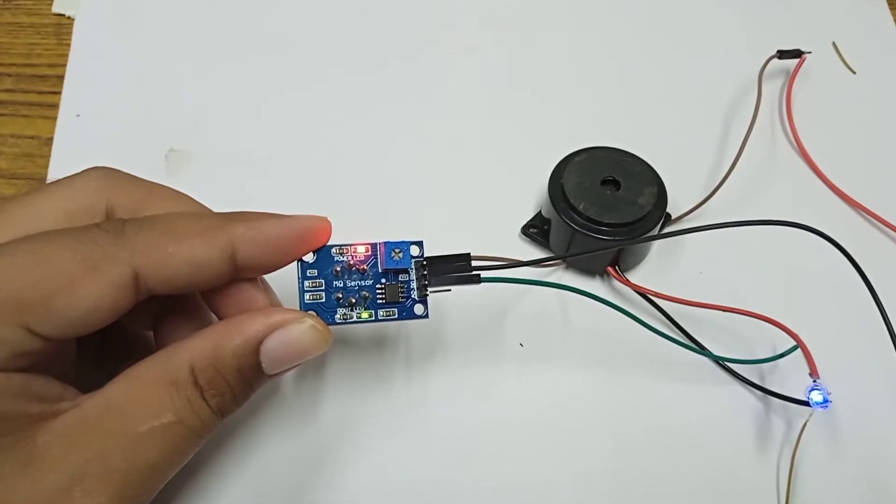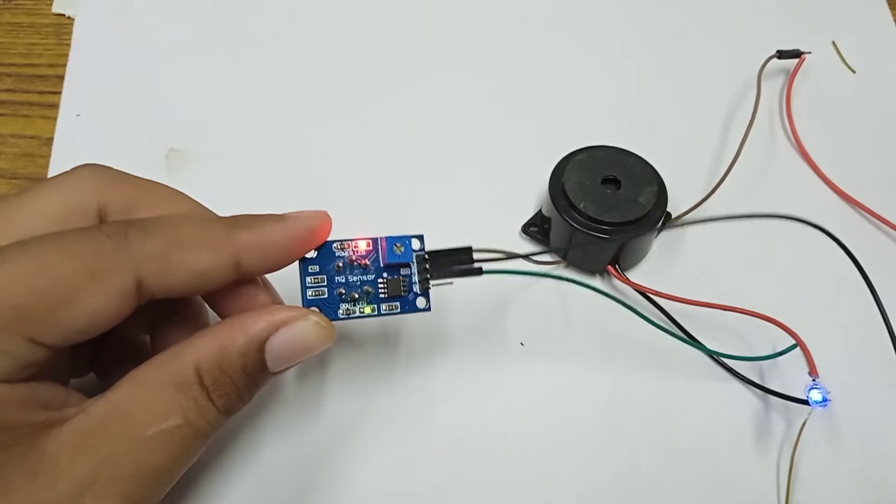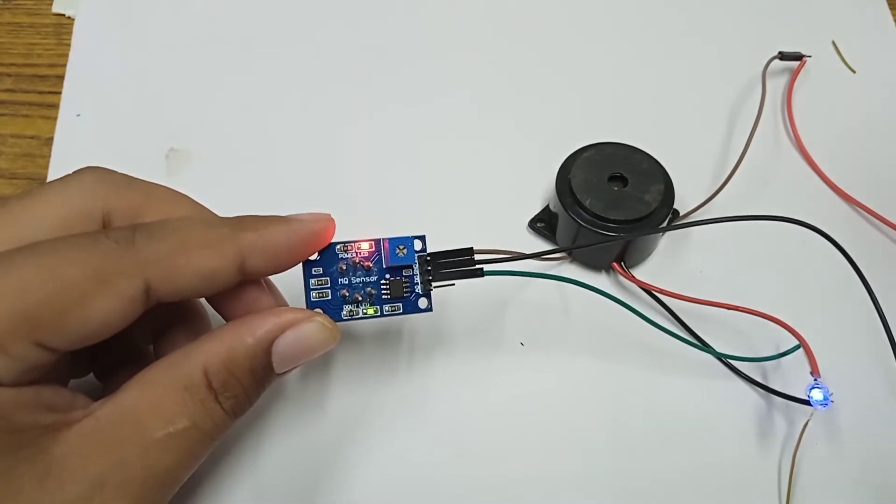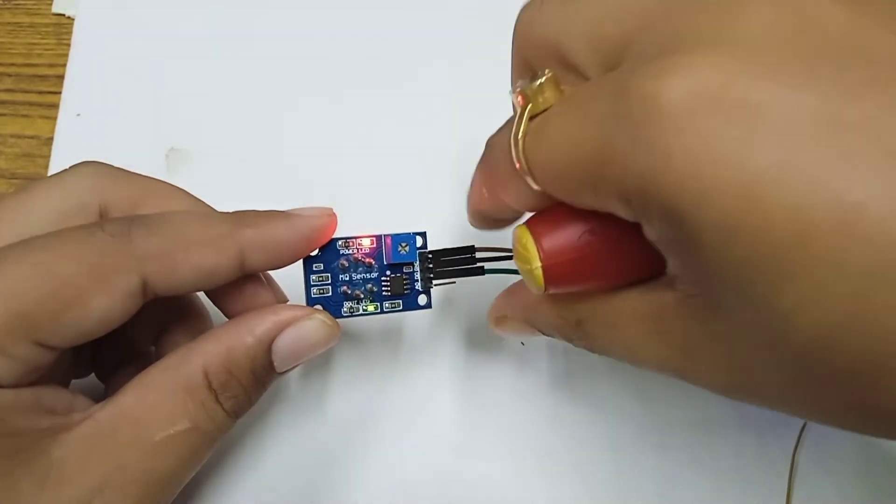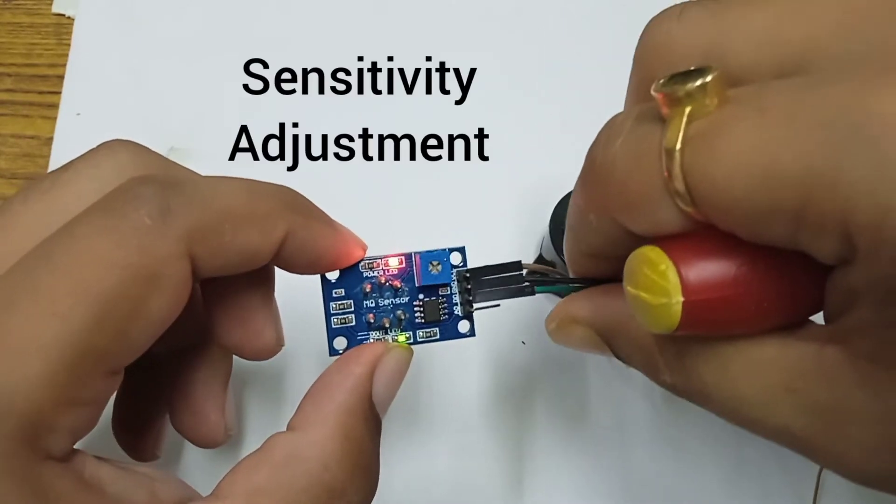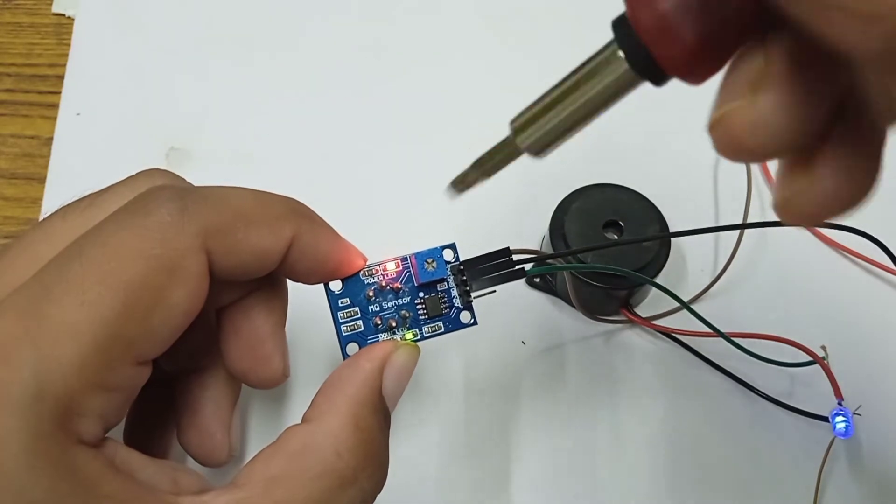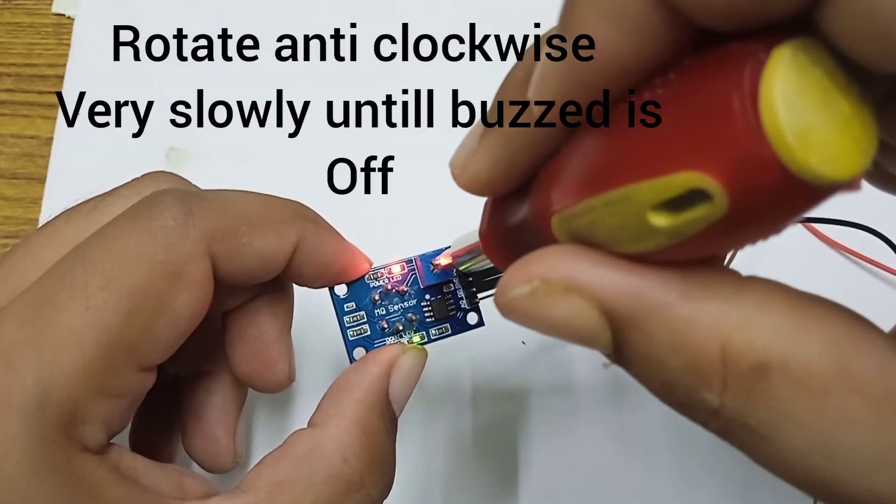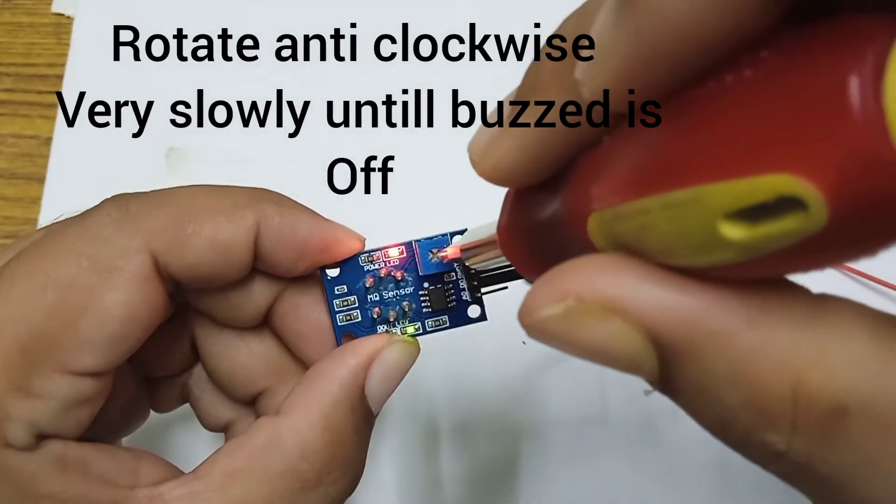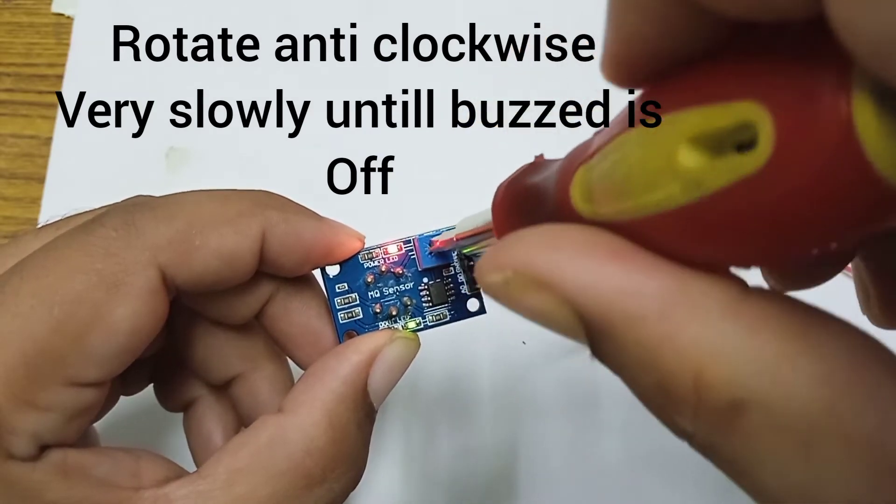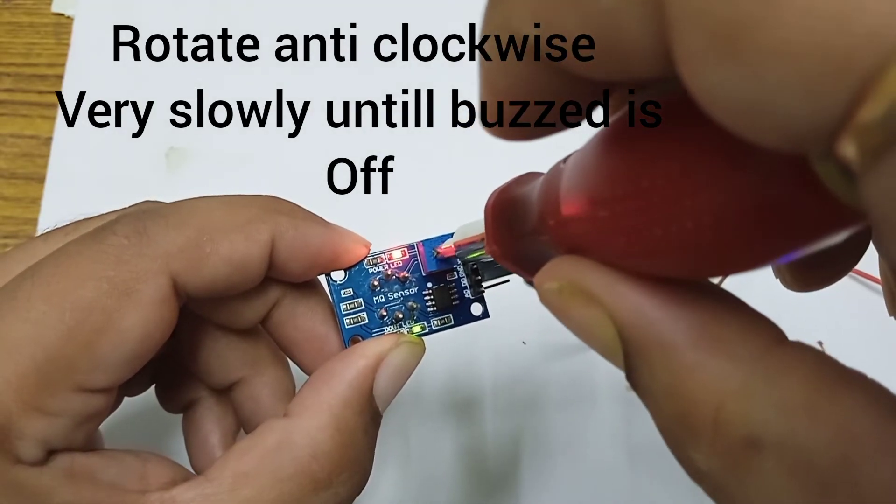Now as you can see, both LEDs are on and already 60 seconds is over, still the buzzer is in on condition. So we have to do some adjustment. Using a screwdriver or any other equipment, you just rotate this in anti-clockwise until this buzzer gets stopped.